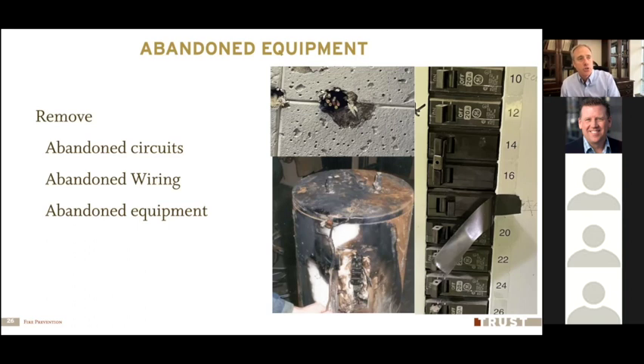And so let's make sure as we cut old wiring from equipment we're not going to use anymore, let's make sure that we cap off and protect the ends of those wires if we can't totally remove them, and also make sure that they're disconnected from the circuit, or that circuit is disconnected altogether. We've had buildings, we've lost entire buildings from this situation.